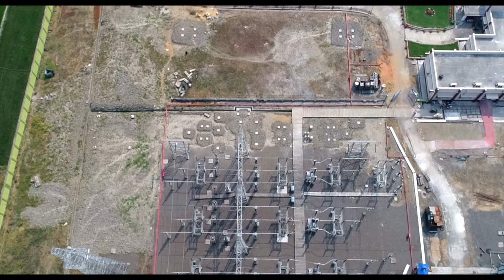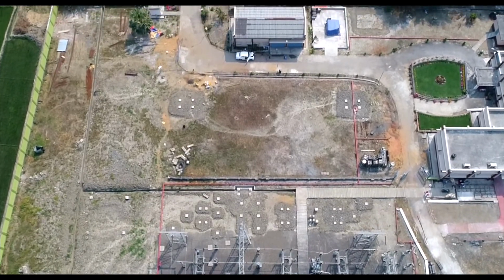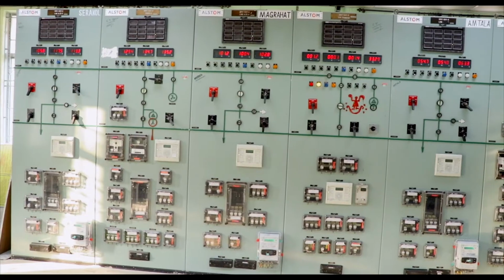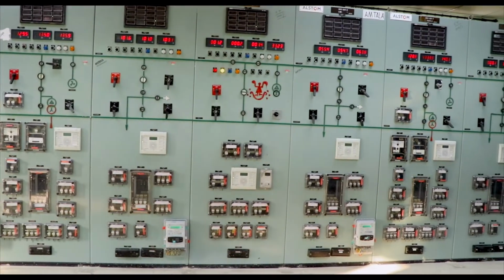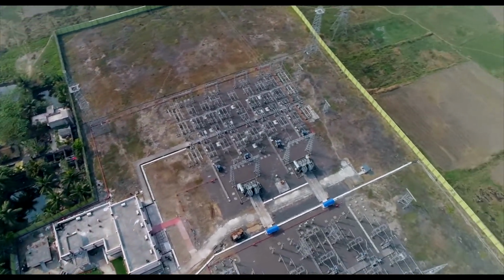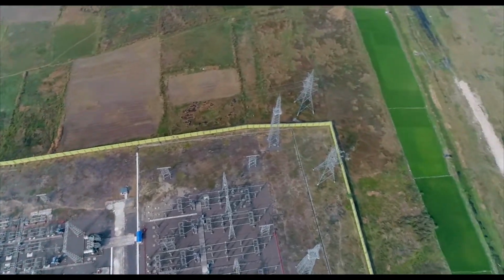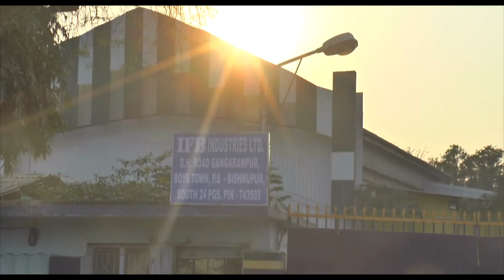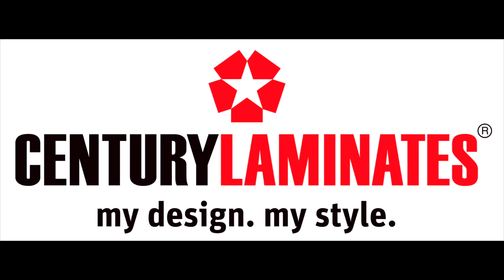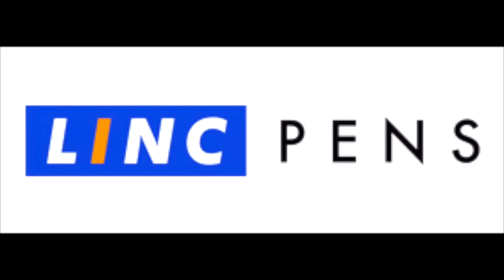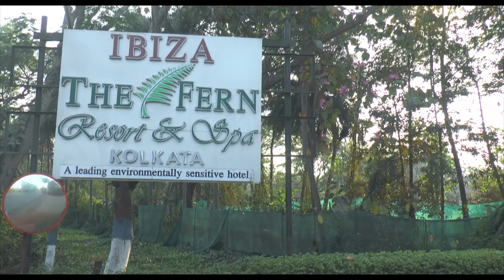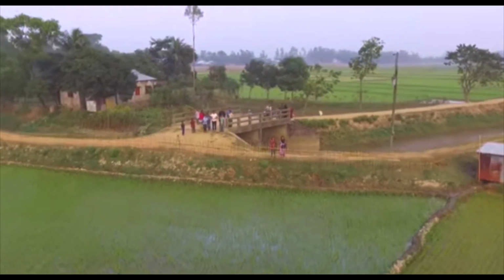We throw this power from this bus at 132 kV level to Behala substation. After that, the remaining part of this power we step down and cater the load at 33 kV level. The substation is responsible for delivering power to very important 33 kV substations, namely Sherakol, Mograhat and Amtola. Through these 33 kV substations, many prestigious bulk consumers like IFB, Amtola Air, Green Ply, Century Ply, Globesyn, Linc Pens, Breathing Earth Resort, Merlin Ibiza and many more villages surrounding this substation are served.